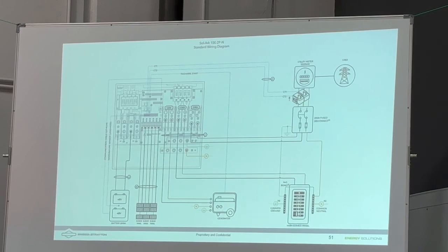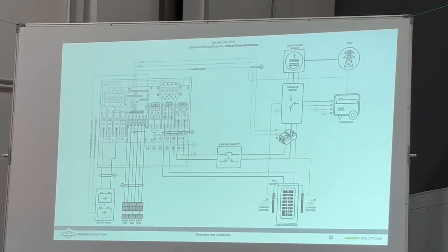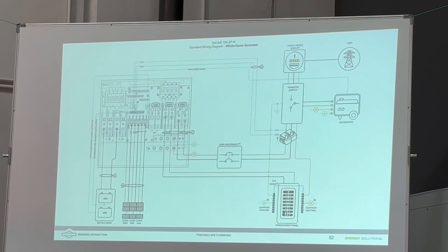You can bring the generator in through the transfer switch to the inverter on the grid port. Now you've got 200 amps that can come off your generator instead of just 80. So like I said, 80 amps is 19 kilowatts continuous power. It can surge up to 100 amps. Probably big enough for most generators, but if you've got a really big generator and you want to be able to pull 200 amps out of your generator, or 160 amps, leave the transfer switch in. The inverter will not backfeed and ruin your generator.